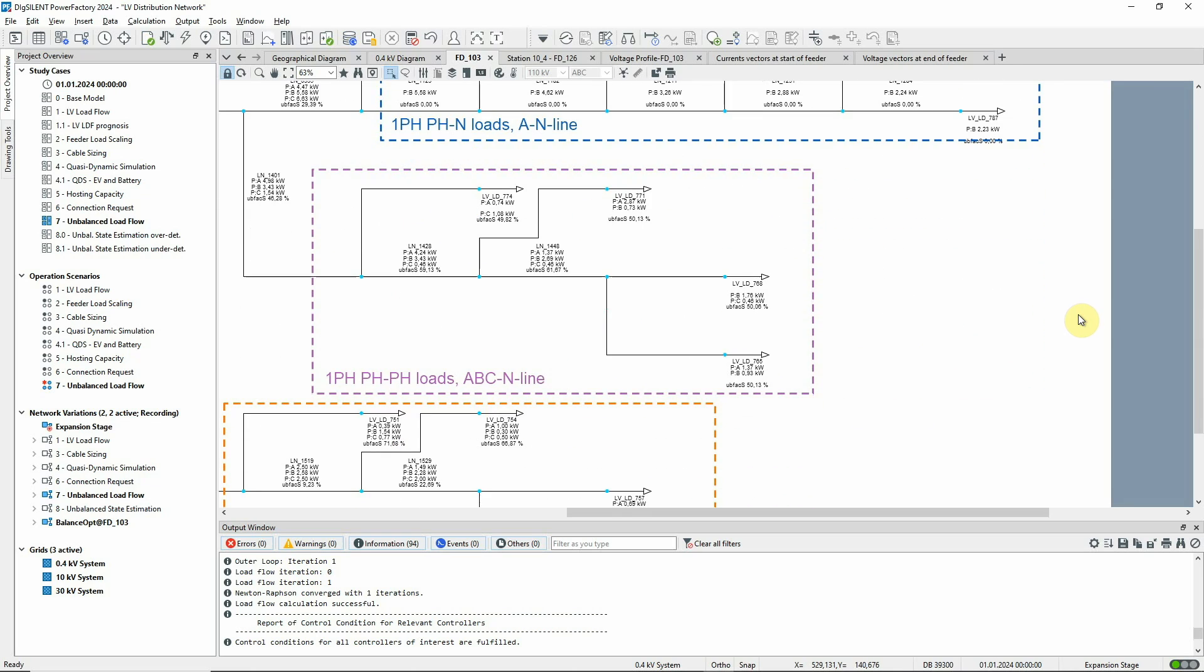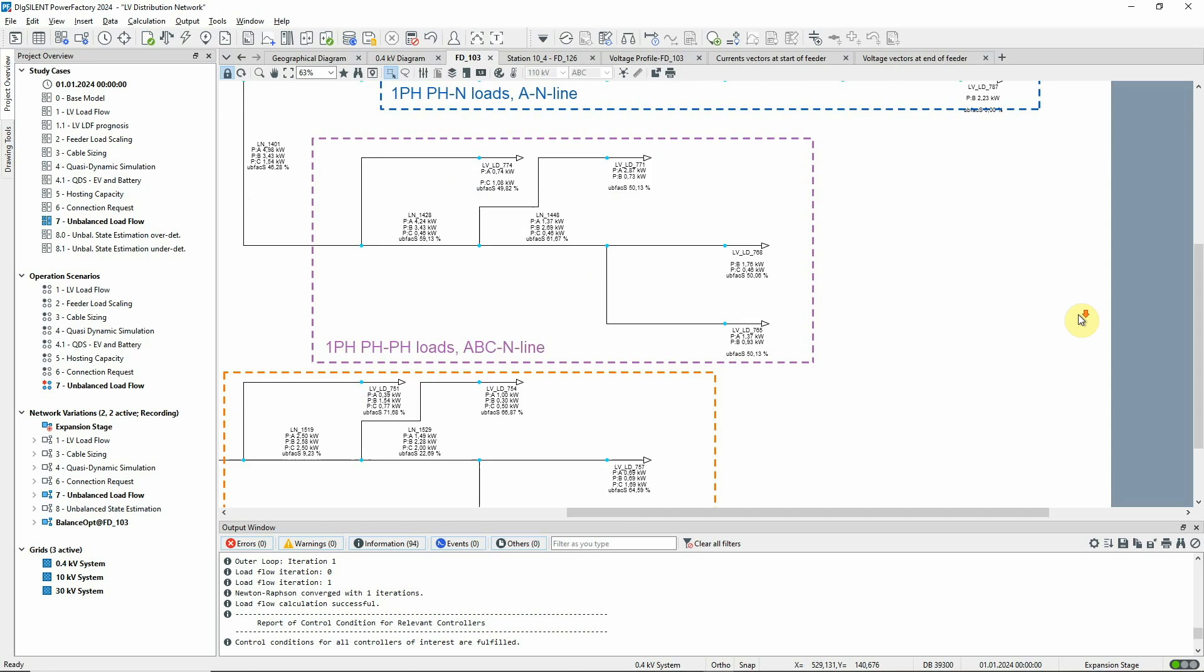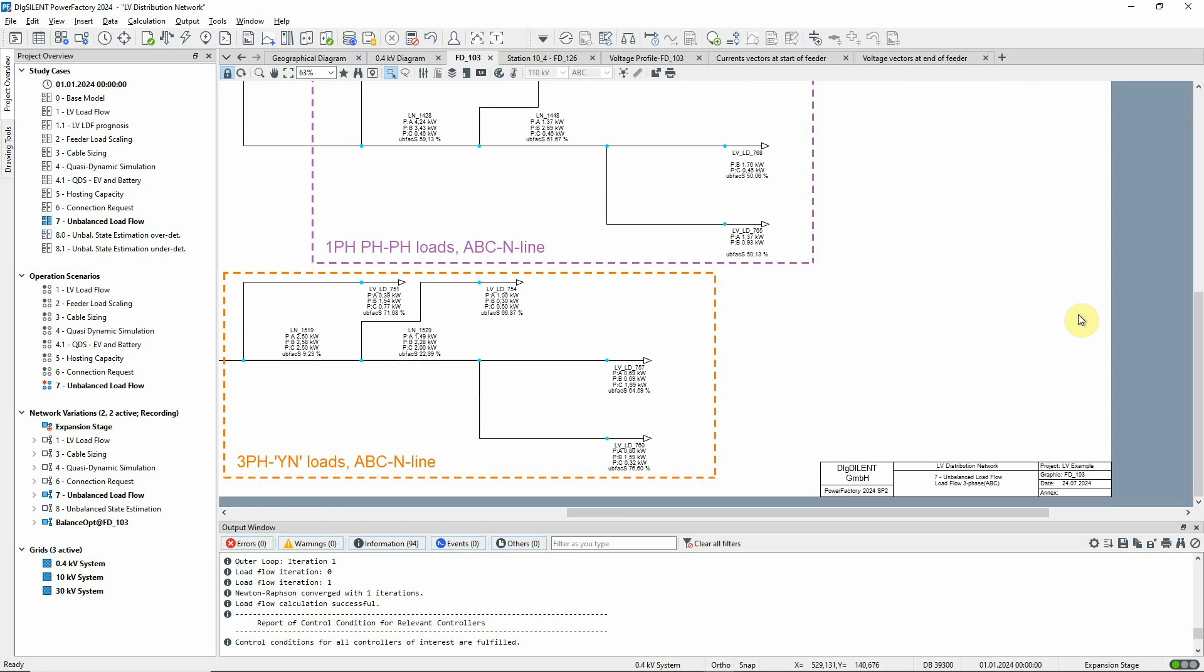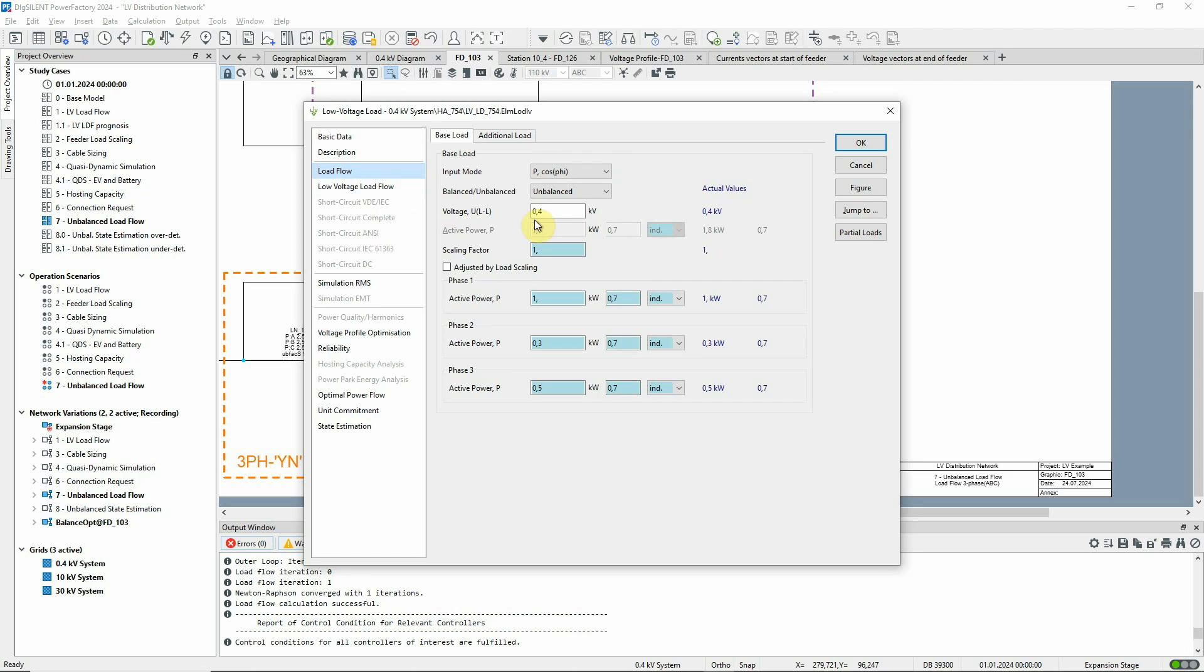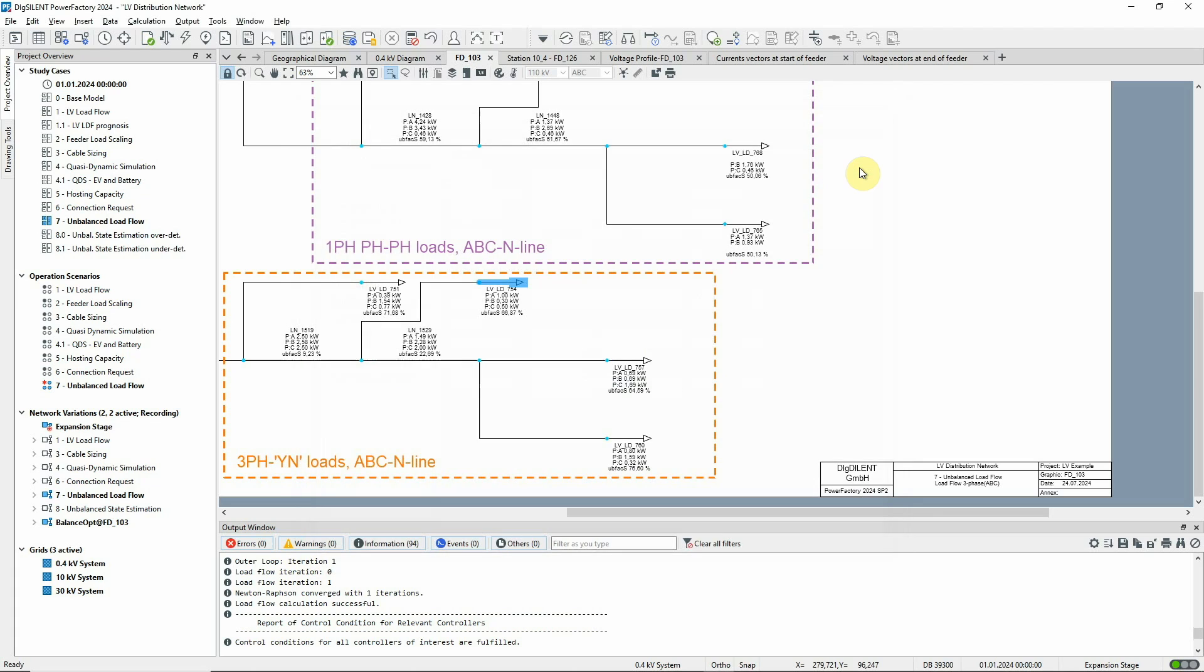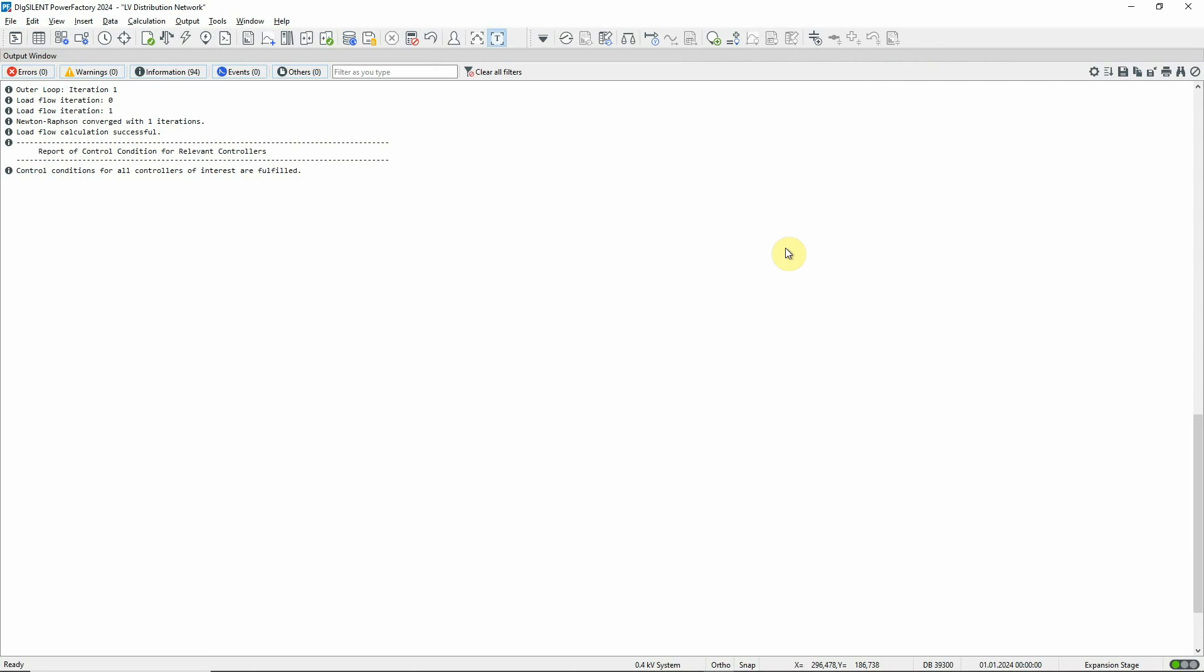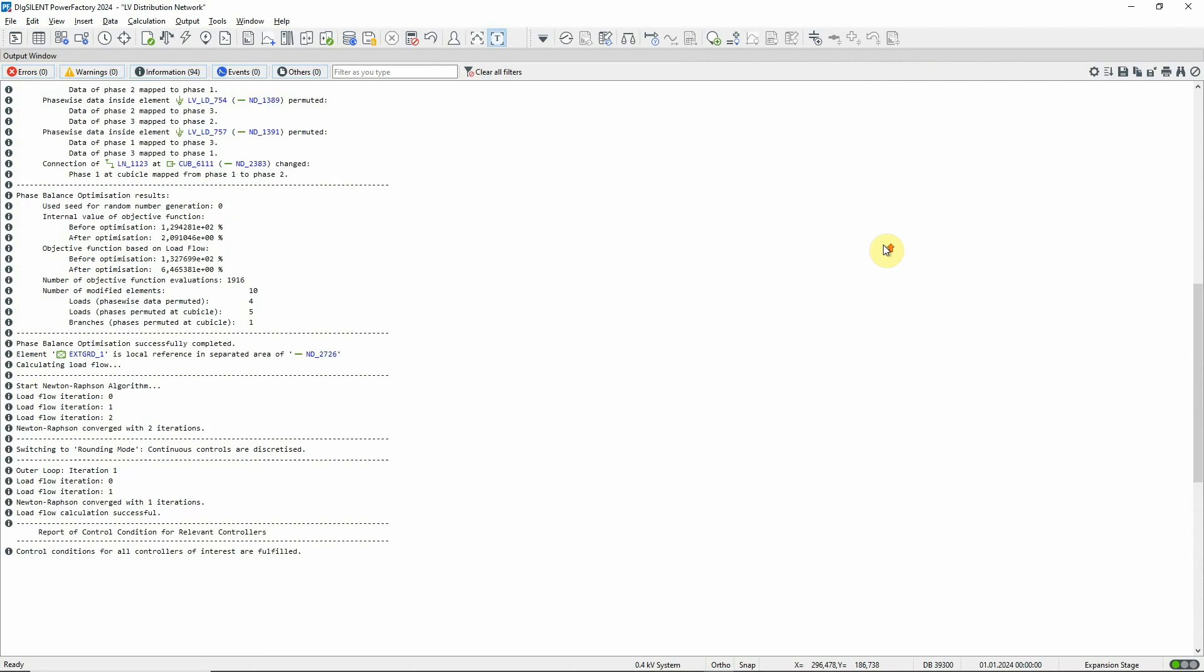The phases of the loads in the third branch have been distributed more evenly. Finally, the phase distributions of the unbalanced three-phase loads in the fourth branch have been changed. You can see details of all the phase changes in the output window.